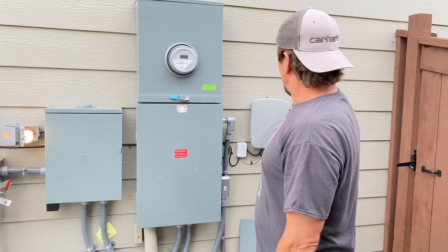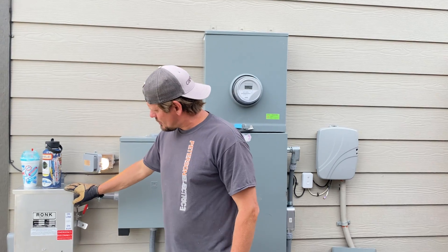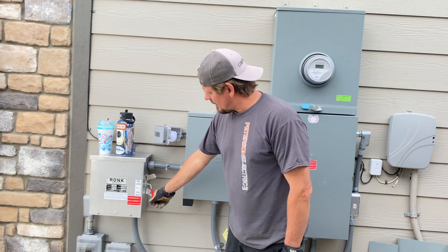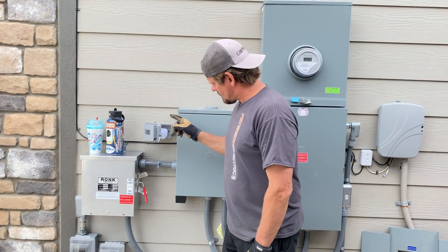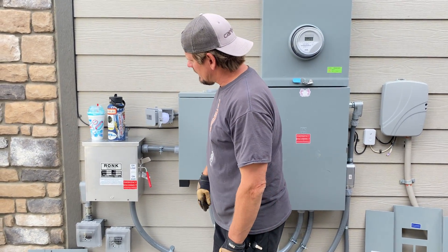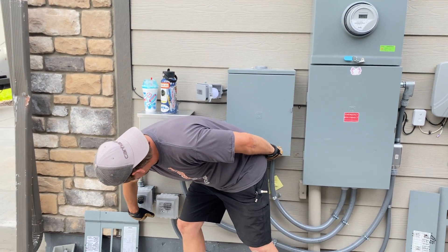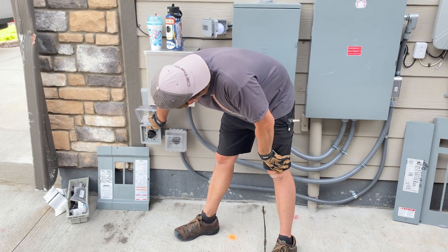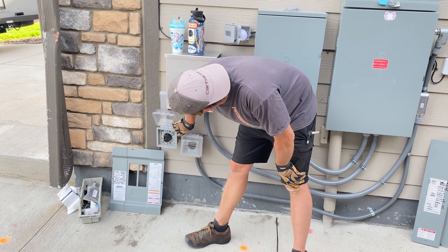This one-inch flex went to my transfer switch — this is my line going into my auxiliary right here. That was definitely just a simple 120-volt plug to trickle charge the RV. If power goes out they can do it on their generator too. This is a roll-up generator switch, 7,400 and 9,400-watt rated, up to 50-amp twist lock, four-wire, by Hubbell.